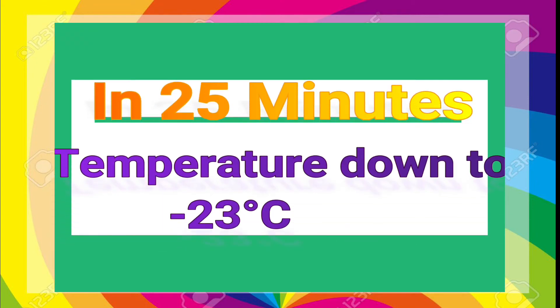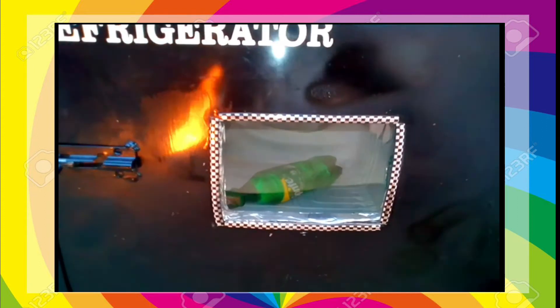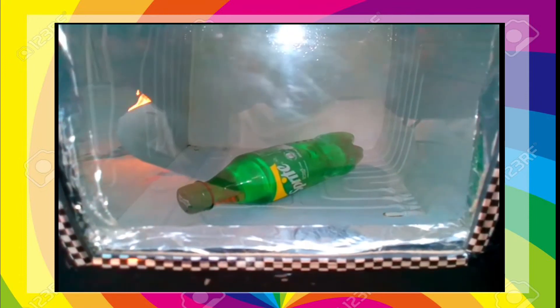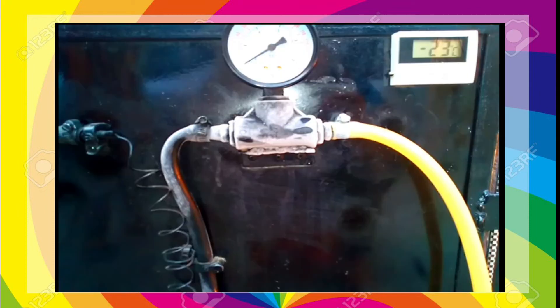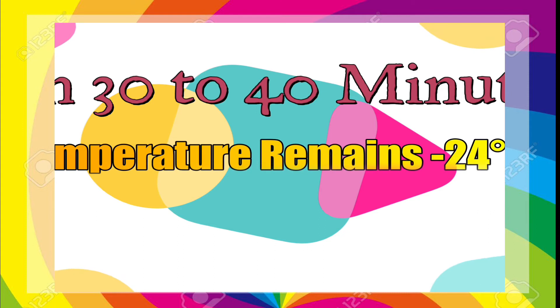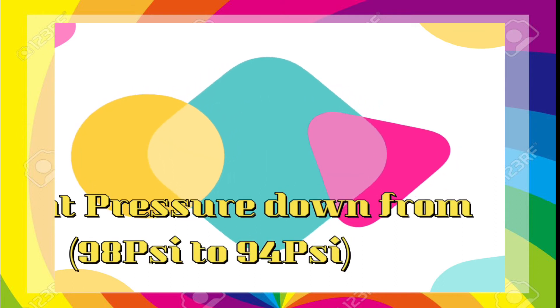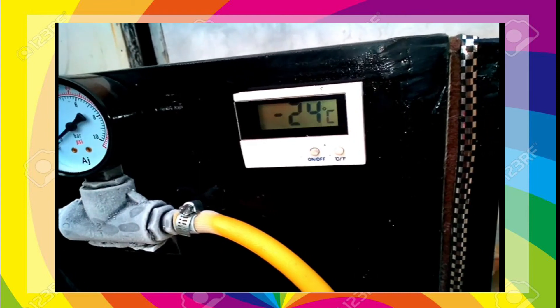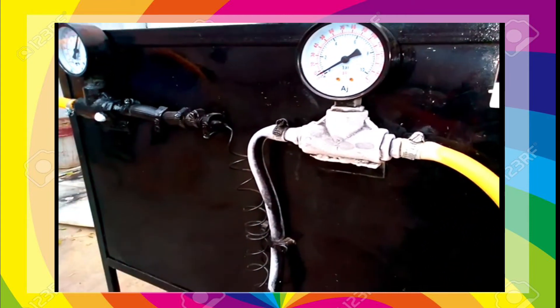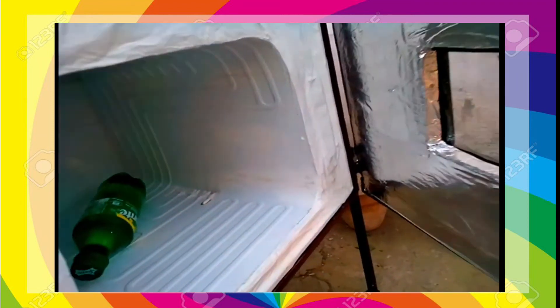In 25 minutes, the temperature is down to minus 23 degrees Celsius. In 30 to 40 minutes, temperature remains at minus 24 degrees Celsius, but pressure drops from 98 psi to 94 psi. And now we finally open the door of the refrigerator.